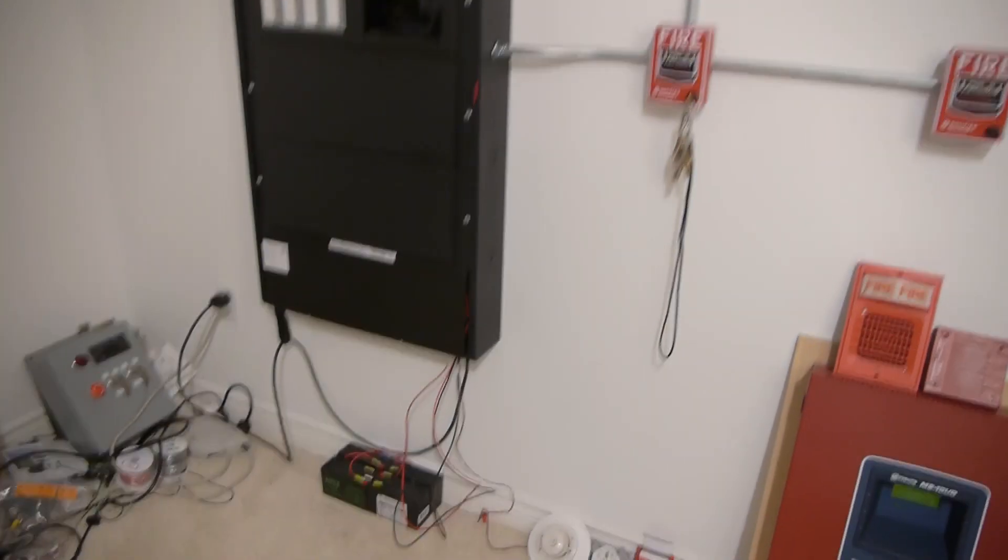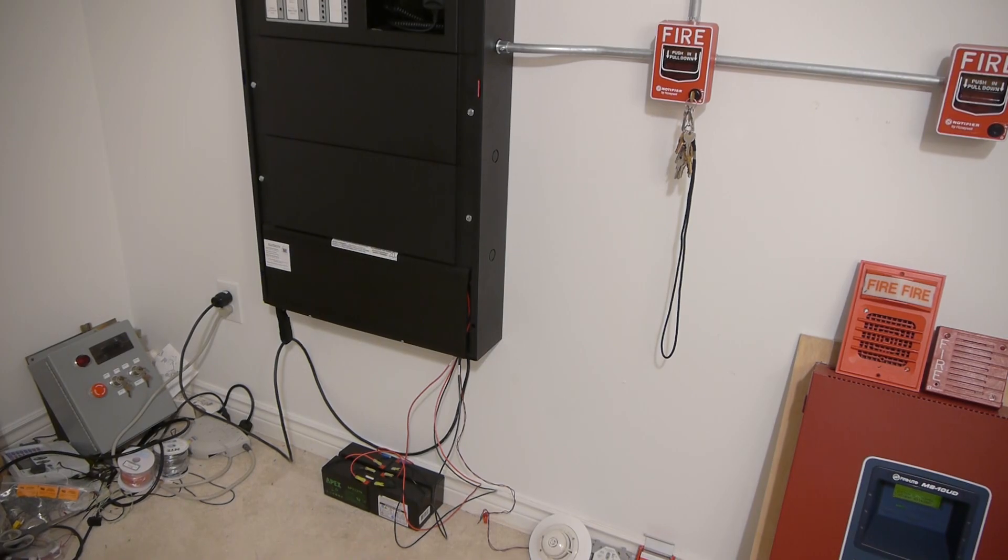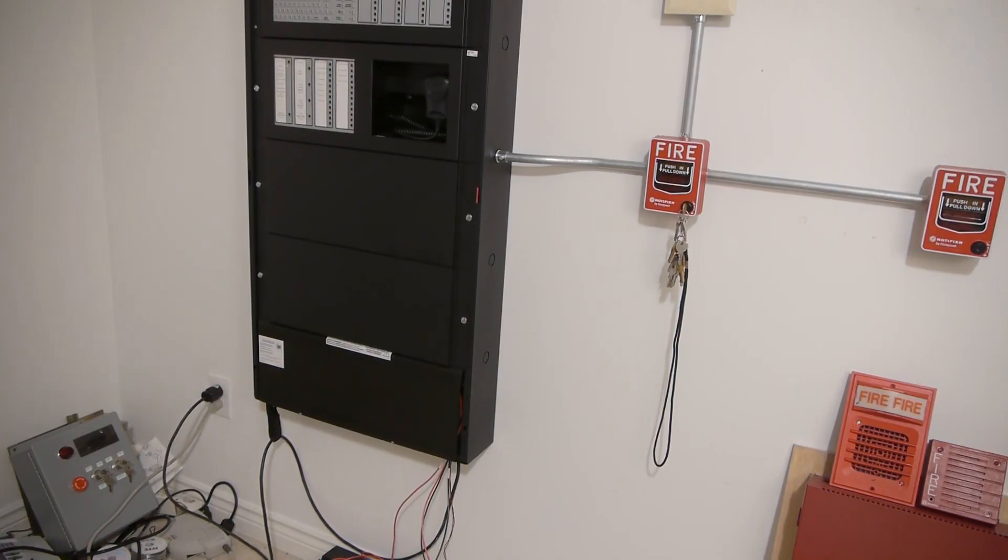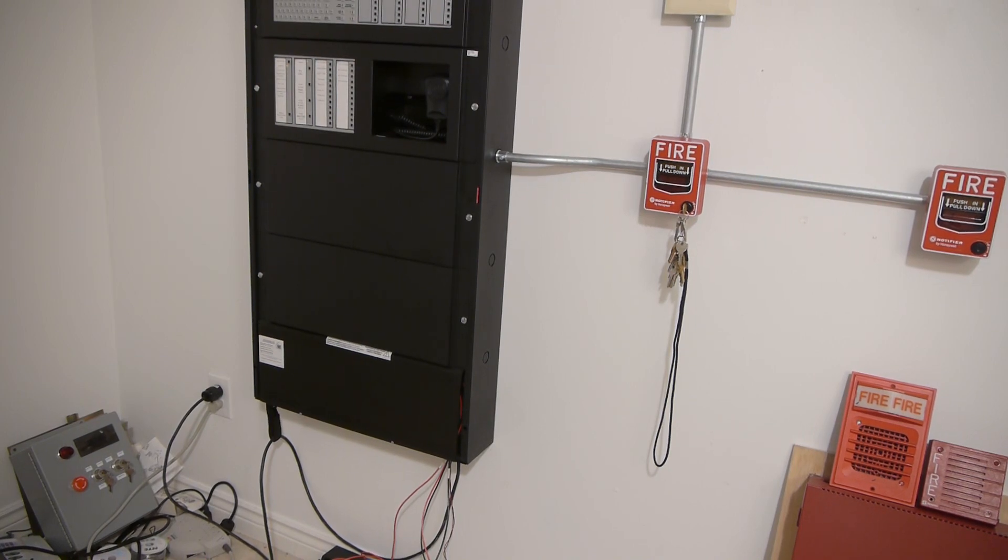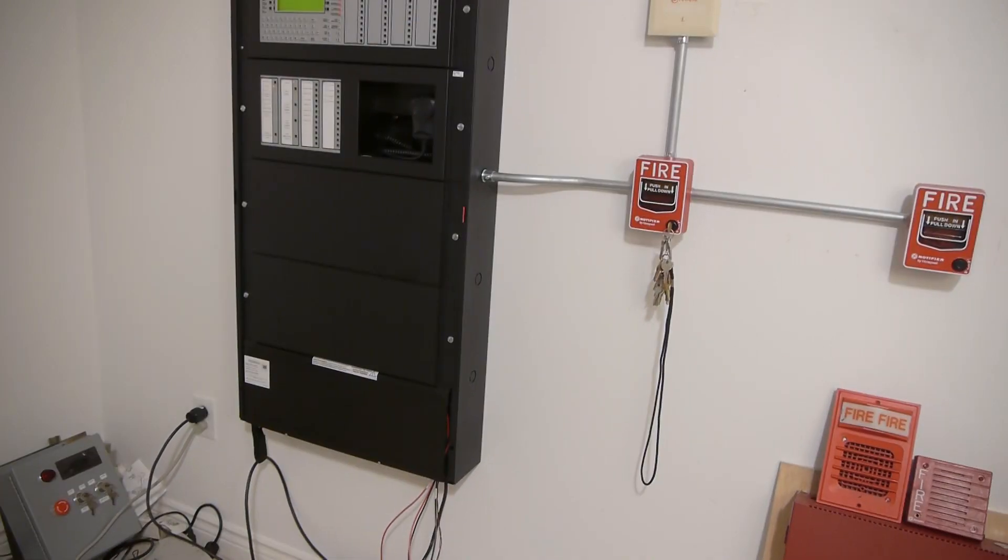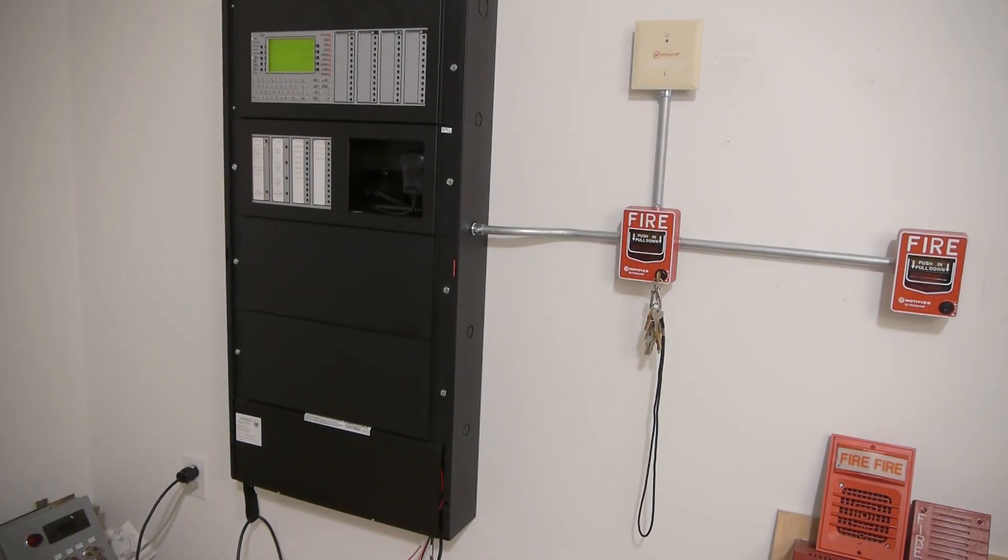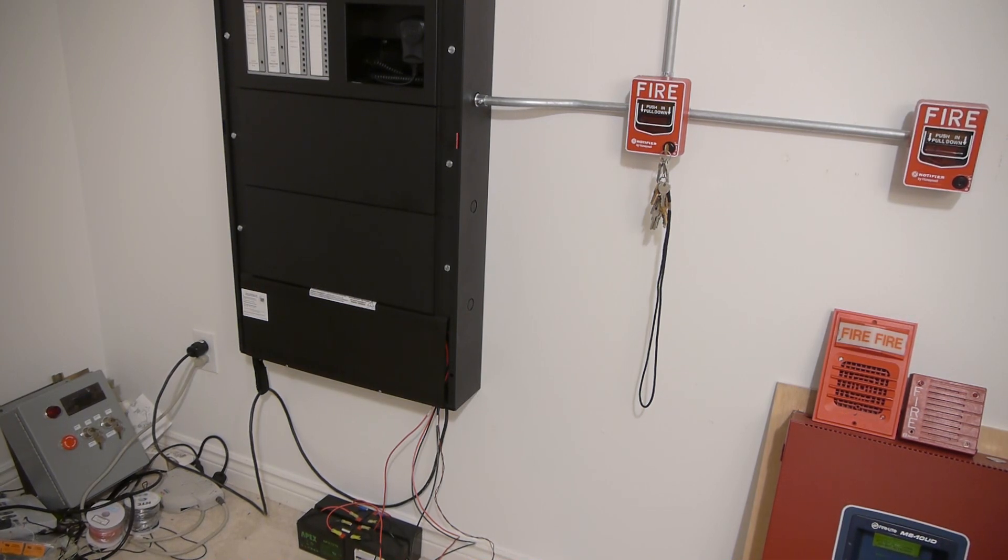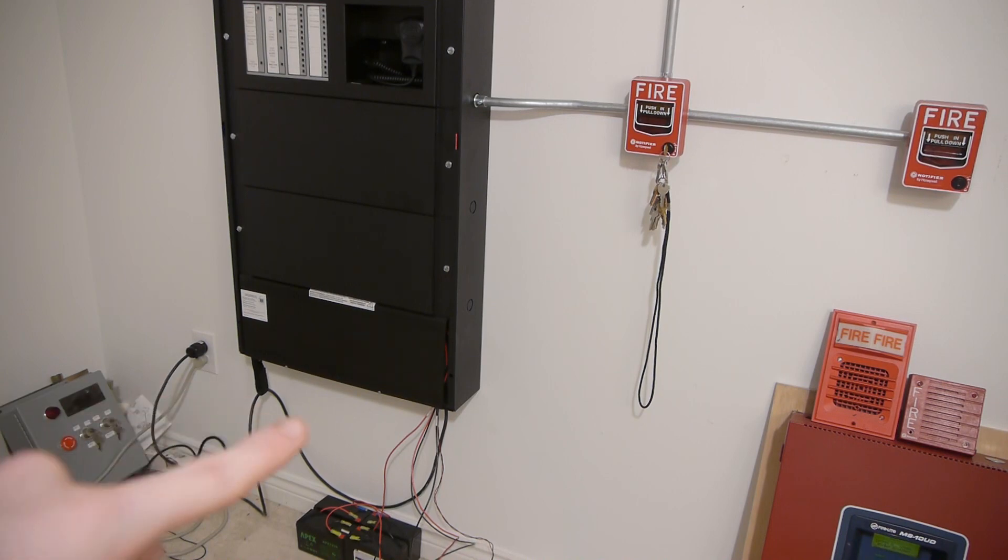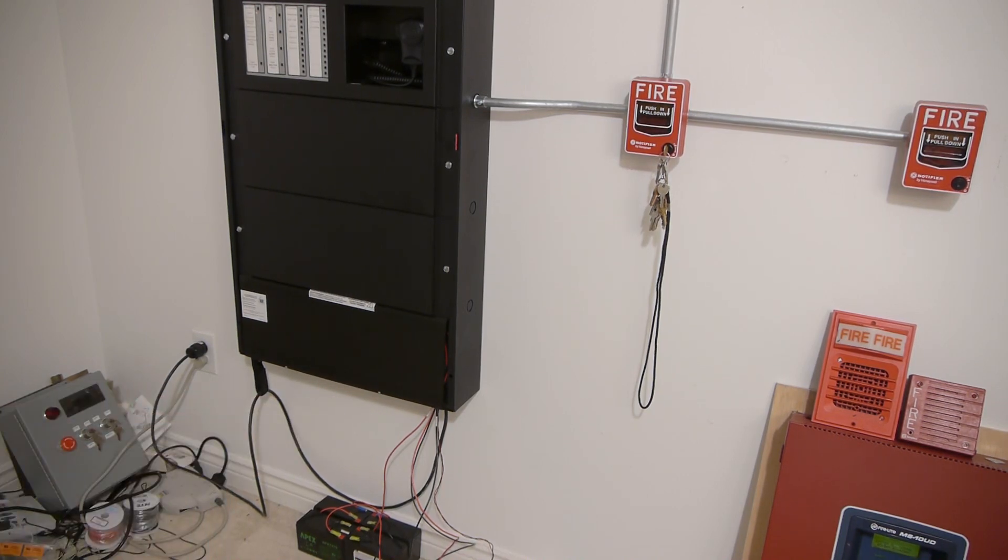And it has this pair of batteries, the front pair right there. And down there at the very bottom, that is a battery bay. It has two power supplies: a Notifier AMPS-24, which is the main power supply for the CPU and the DVC, and an ACPS, which is the NAC power supply. That normally gets mounted in a separate enclosure, but I had extra room down there, so it's right there.